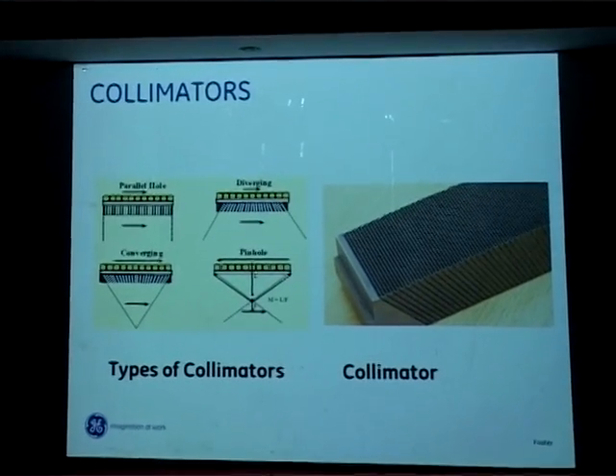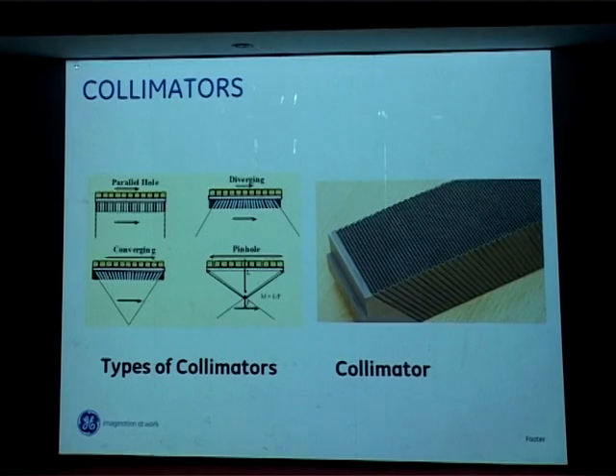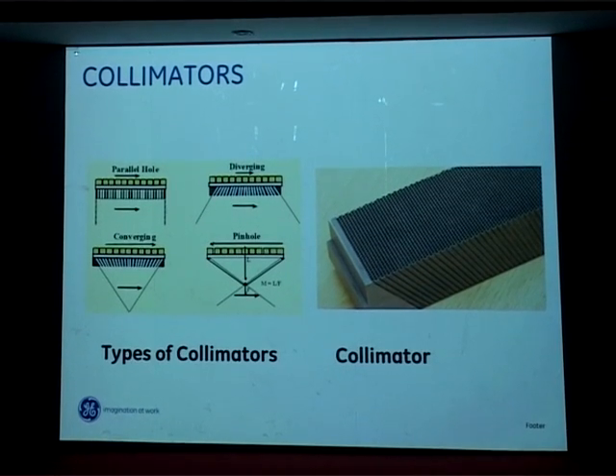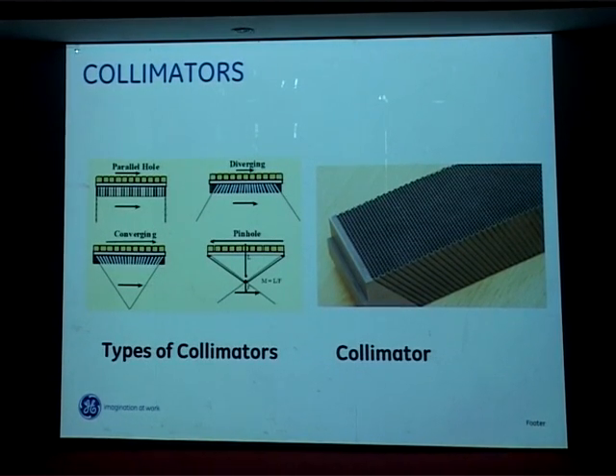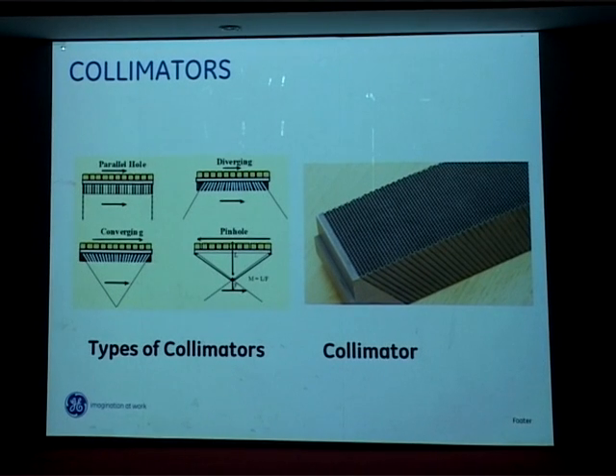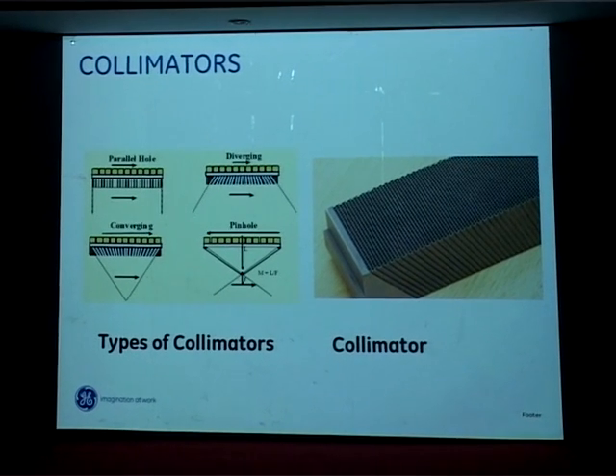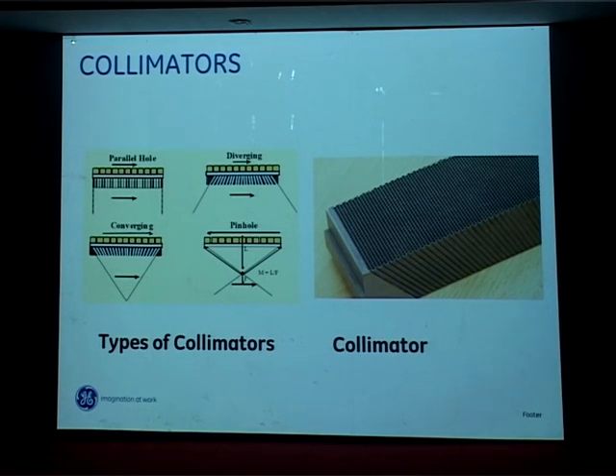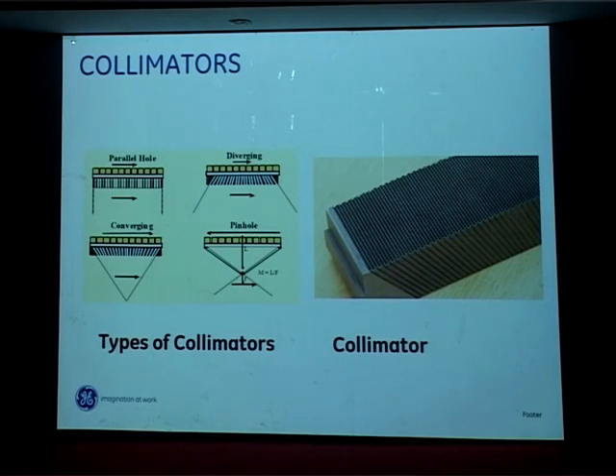On the right-hand side is a diagram of a collimator. You can see the hexagonal holes through which gamma rays pass and are detected by the detector. There are different types of collimators: parallel-hole, diverging, converging. The most commonly used collimator is the parallel-hole collimator.